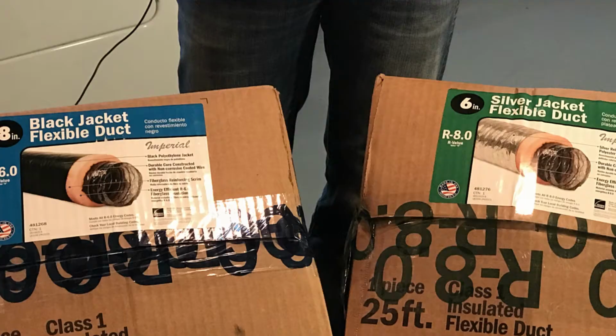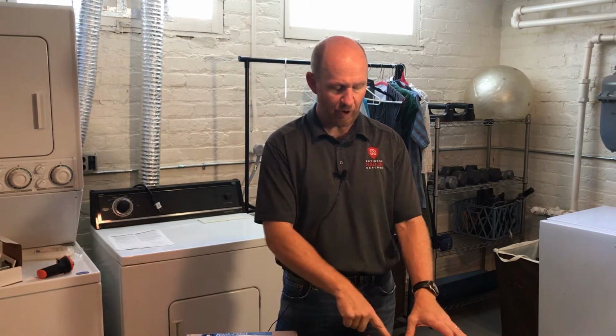When routing the ductwork from the ERV to the outside and also internally, you're going to use flexible insulated duct, okay? And so here's two examples. You have right here an 8-inch R6 value flexible ductwork. And then here's an example of R8 6-inch ductwork. Obviously, the larger ducting, an 8-inch duct, will give you better airflow, so better performance of your system. 6-inch isn't horrible. You still have pretty good airflow with that, but less than the 8-inch. And then with this R8, that's a higher insulation value than the R6 over here.